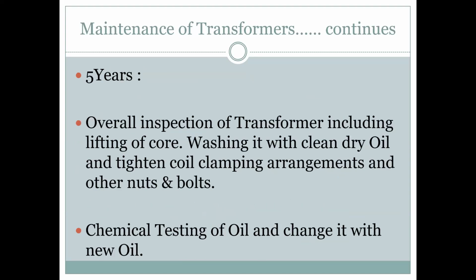We always suggest that in spite of filtering the oil, you must change the oil after every 5 years, because it loses its acidity content and chemical content. Although you will still get the BDV, the insulation characteristics will go down. So it is better to change it, and do not mix new oil with old oil, because the quality will come down. It is like putting 1 drop of lemon in milk: it will spoil it.